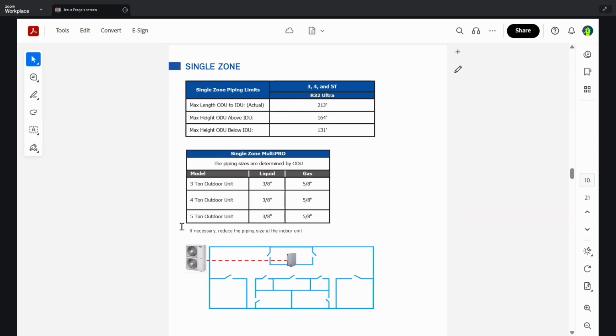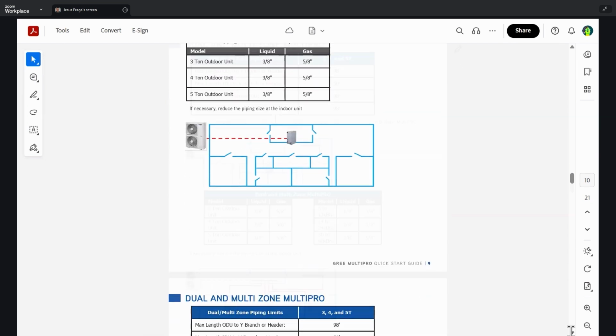So one of the key differences between the 410A and the R32 is the line set connections at the outdoor unit. For the R32 MultiPRO unit, all the line set sizes are 3/8 by 5/8. That's 3/8 liquid, 5/8 gas. And if it's necessary, please reduce the piping size at the indoor unit. So below is an illustration of a 1-to-1 and how to centrally locate that unit.